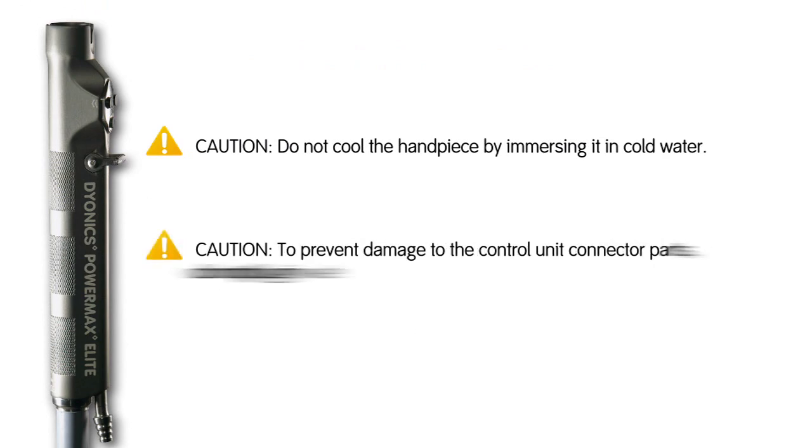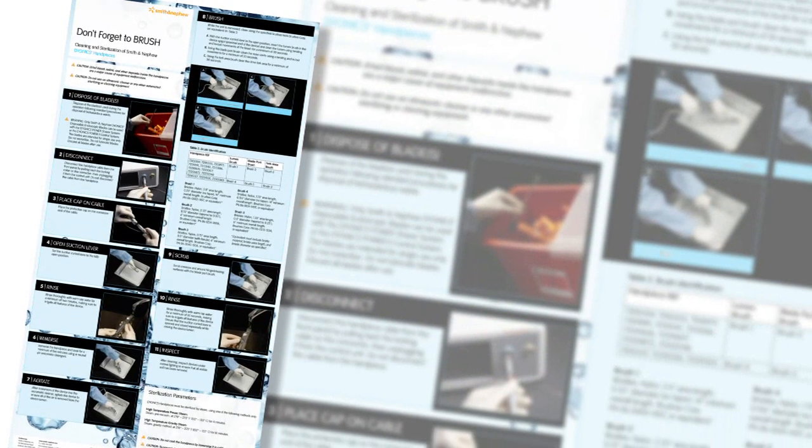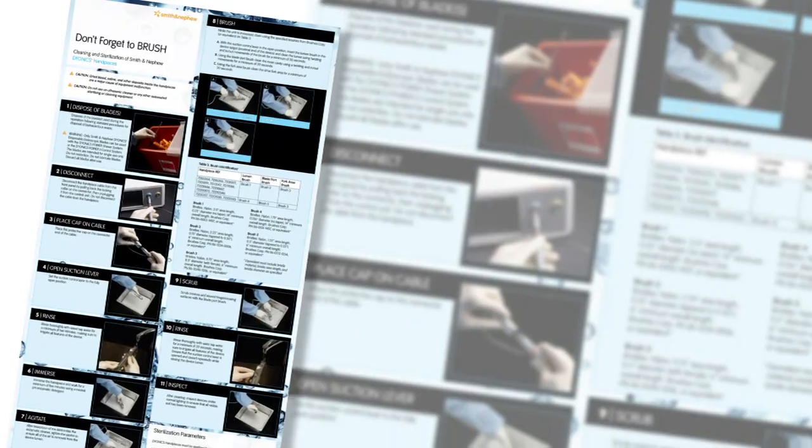Caution statements: Do not cool the handpiece by immersing it in cold water. To prevent damage to the control unit connector parts, do not plug in wet. Ensure that cleaned or sterilized cable connectors are completely dry prior to connecting to the control unit. Thanks for watching this training. We hope you found it helpful for learning the critical steps in the proper sterilization of these devices. If you ever need to refer to the steps described in this video, please ask your Smith & Nephew sales representative for a Dyonics cleaning and sterilization poster, which describes the same steps you've just seen.